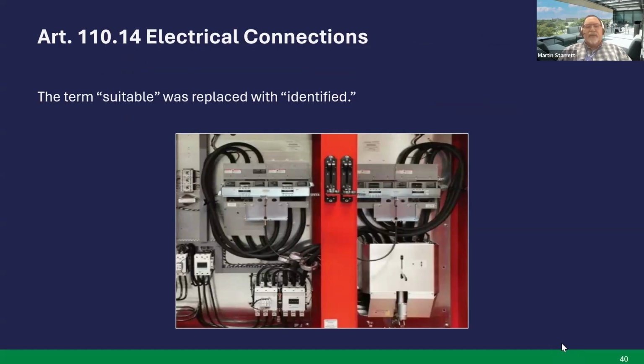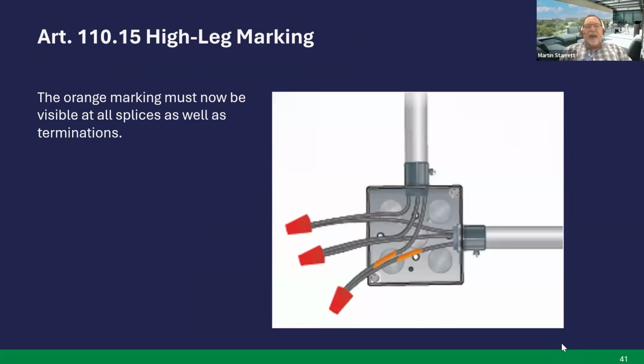110.14, electrical connections. The term "suitable" was replaced with "identified." So now you'll be looking for identified connections and not suitable. Next slide. The high-leg marking, the orange marking, must now be visible at all splices as well as terminations. Currently in our electrical ordinance, we tell you that we have to have the marking at the splices and terminations. So that's something that's already here in Austin.